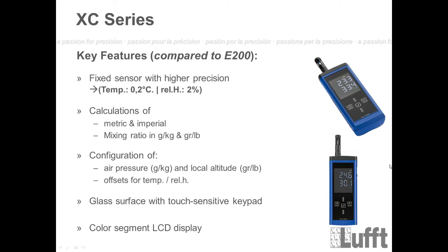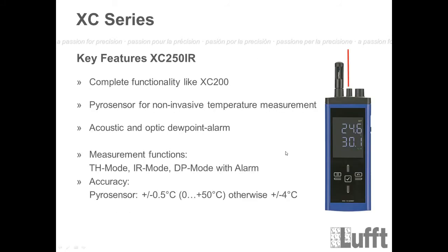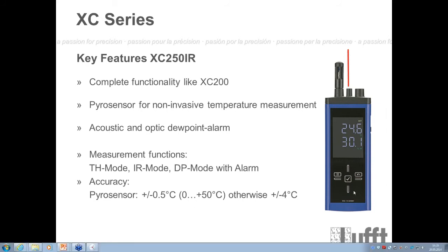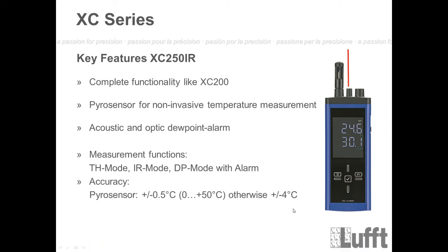If we talk about the accuracy of the pyrometer, it's different. As I told you before, the pyro sensor has an accuracy range between 0 and 50 degrees, where you have an accuracy of plus minus 0.5 degrees. Otherwise, outside this range, it's plus minus 4 degrees. For the relative humidity, it's full range information, so plus minus 2% is over the whole range, 0 to 100%.